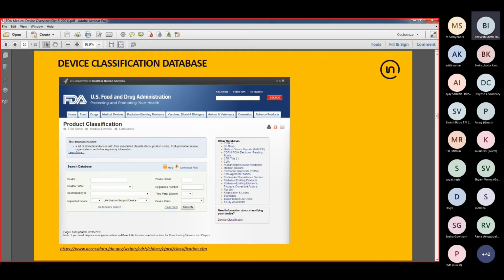This is FDA's formal device classification database, and the information you find here supersedes anything else any regulatory consultant will tell you. If there is a conflict in the message you are getting regarding classification, what you find on the FDA website is the final decision by the regulatory authority. If you have a device that is novel and for which a classification doesn't exist, then yes, there are ways in which inquiries can be made to the FDA. I'll cover a bit on that later, where you can explain your product to FDA and ask them to provide insight into the classification and the regulatory requirements. But this is the FDA device classification database page.